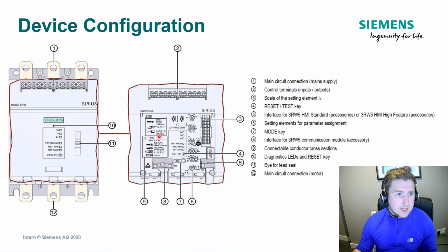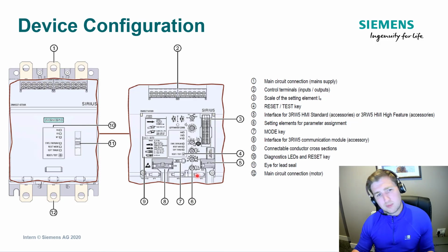Number 9 here shows you what type of connections you can make with what conductors and what sizes. Here, number 7 is the mode key, and number 6 here are the potentiometers which you can set, and they're very similar to the 3RW40. You've got a ramp down function, the starting voltage, the ramp up time, you've got the current limit function, you've got the operational current of the motor, and then you've got the overload integrated into the unit as well.